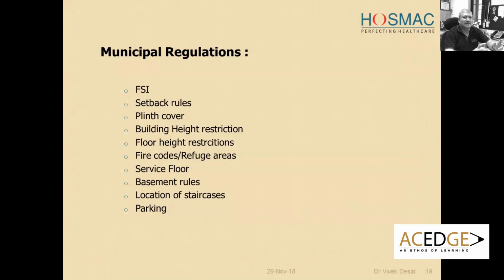So that is a must in hospitals, and this is generally about the operation theatre, because in hospitals each operation theatre will need one air handling unit. Every operation theatre needs a dedicated AHU. So what we do is we put the operation theatres on, say, the second or third floor. Then we put a service floor so that all AHUs are on the service floor. And then we take all inpatient floors on top of it, so that all the plumbing which is coming down, because generally toilets are towards the corridor, gets diverted at the service floor and goes out of the building. So that service floor is a very important criterion for us.